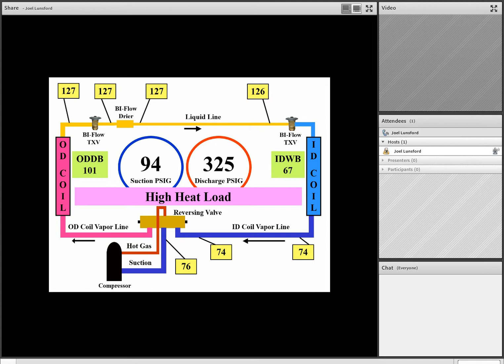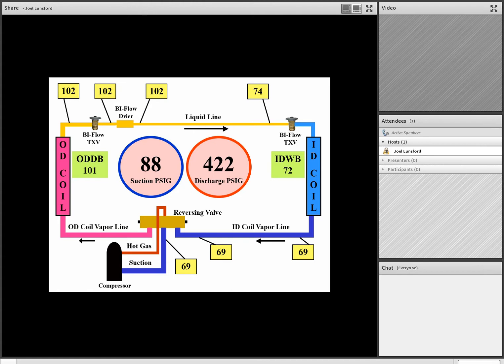In this next example, we have an R410A service call. Our suction pressure is 88 pounds of pressure, which is low for an R410A unit. Discharge pressure is elevated. It should be running about 360 or so, or maybe 375. However, it's elevated. So our suction pressure is low. Our liquid pressure is high. And let's do our superheat on the indoor coil together.